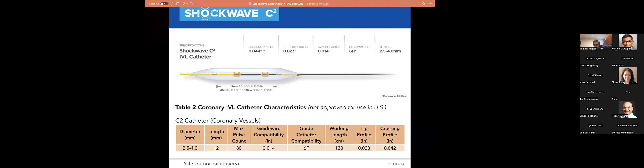This is the distribution of the length. So here's the distal emitter, the distal radiopaque marker. So what you're going to see is that distal radiopaque marker and that proximal radiopaque marker. That's the 12 millimeter distance between the two. And then the emitters are actually off center, so they're not exactly in the center of those radiopaque bands. They're a little bit off center. So the first emitter is 2 millimeters distal to the proximal radiopaque marker, and then there's a 6 millimeter gap, and then you have the final emitter. And the acoustic pressure actually has been shown to decline just 3 millimeters away from those emitters. So if you really don't get it right where you want it, you are going to lose a lot of the effectiveness of the device.